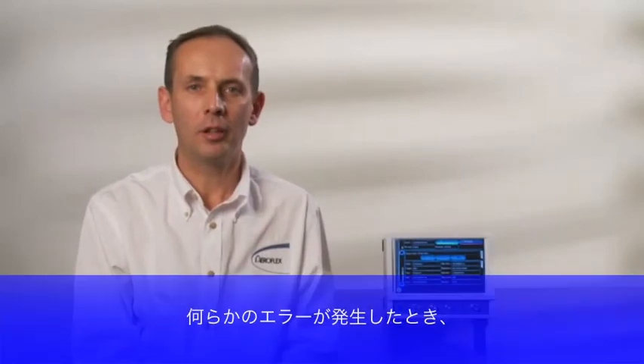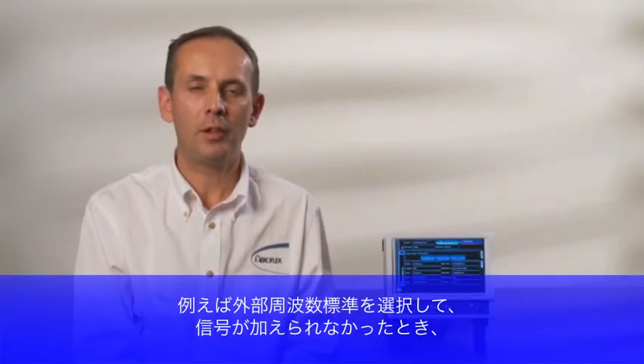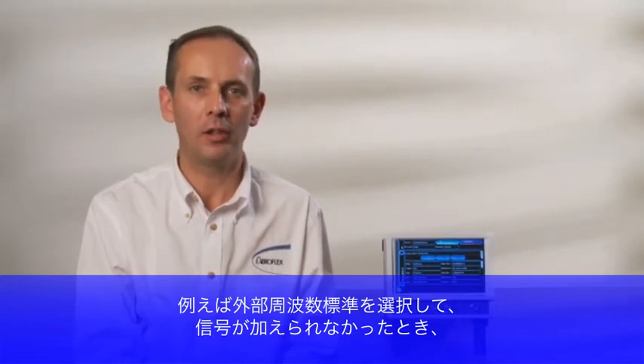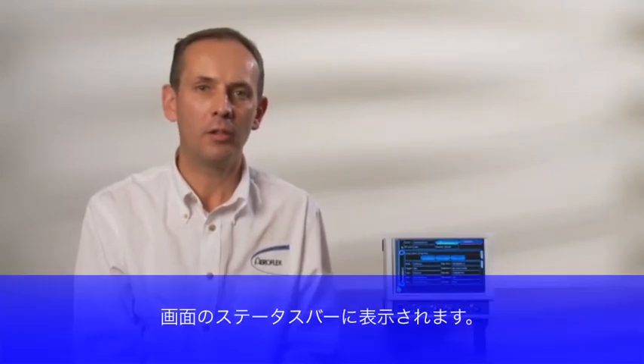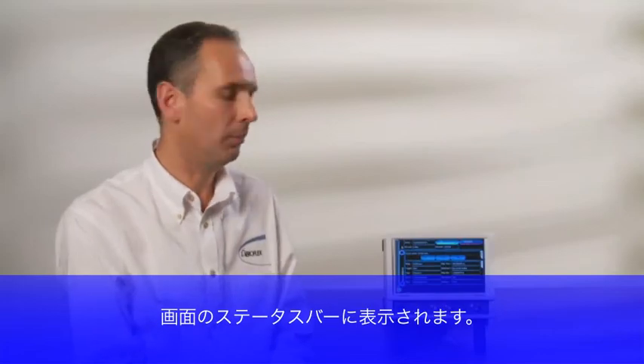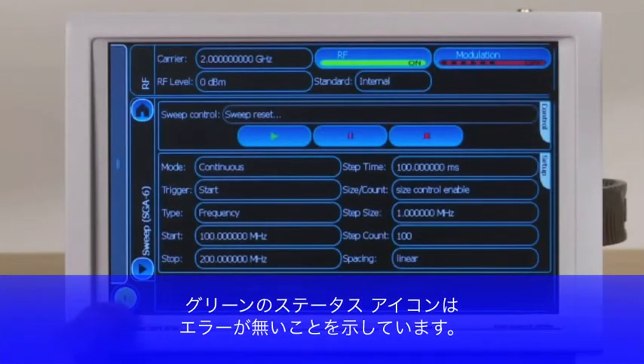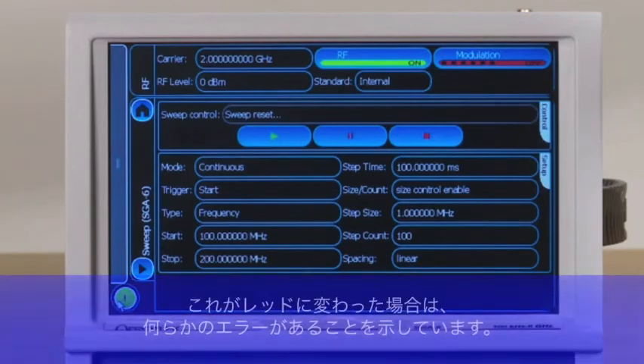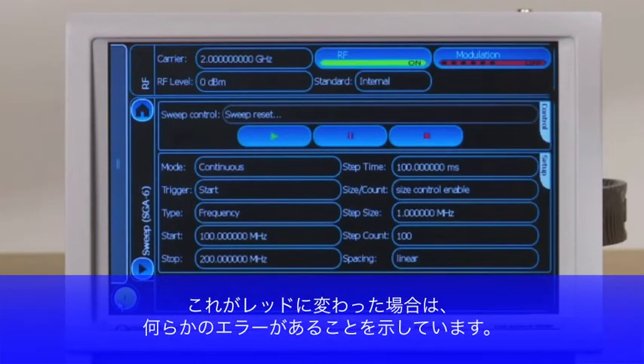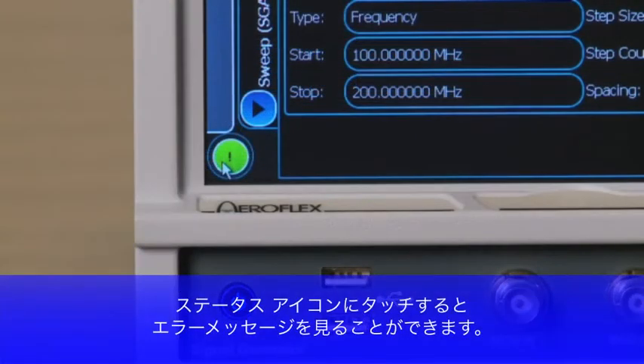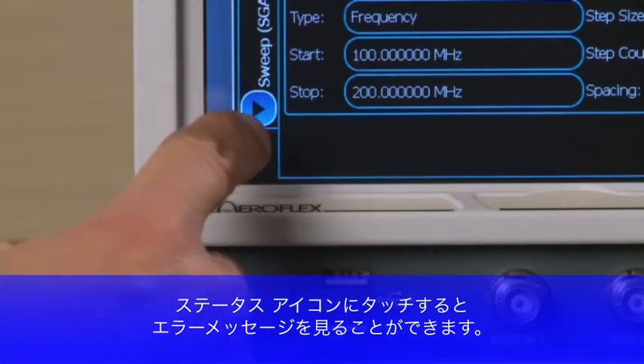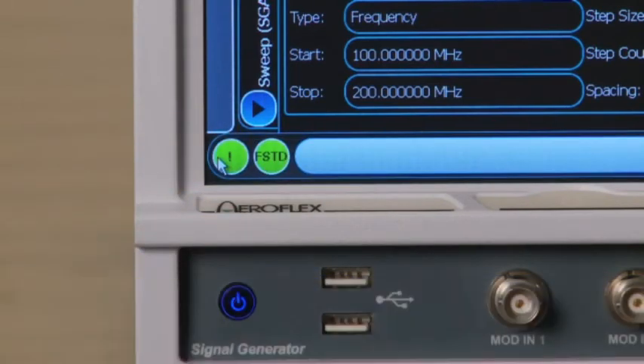Any errors which occur, for example, if the SGA is set to external standard but no external standard signal is applied, are reported in the status bar at the bottom of the screen. The green status icon shows that no errors are present. This will turn red should any errors occur. Touching the icon brings up the status bar such that the error message can be viewed.